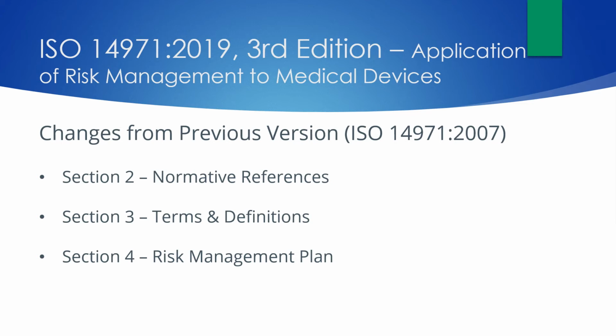New terms that are included in the updated standard include benefit, which is a counterpart to the existing definition of risk, state-of-the-art, and finally, reasonably foreseeable misuse. Reasonably foreseeable misuse is defined as any improper use arising from readily predictable human behavior, according to the standard, and may or may not be intentional. Section 4, which is the Risk Management Plan, has an addition that states a method to evaluate the overall risk, and the criteria for acceptability of the overall risk shall be included.